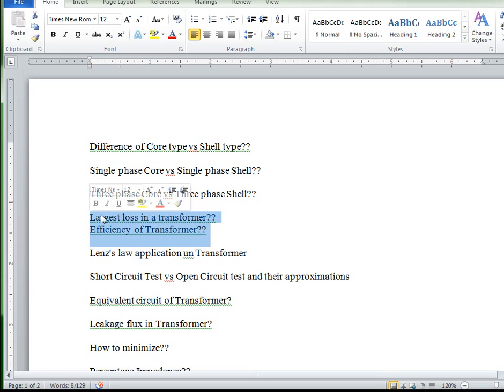So the maximum efficiency is designed in such a way that the largest loss in a transformer is always copper losses. Remember, they are variable and they are the largest. And whenever we are designing a transformer for the distribution side, we always keep the core losses small.